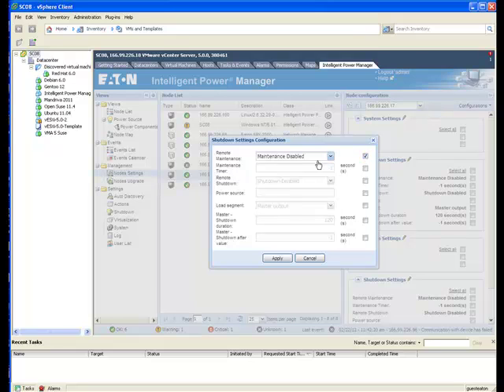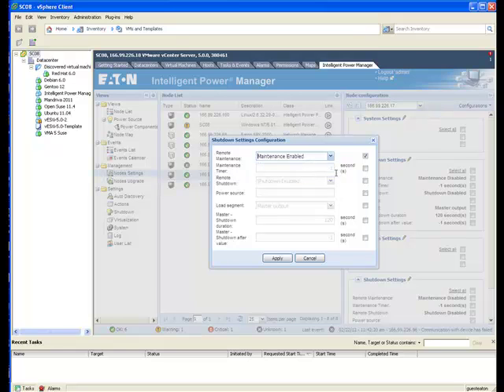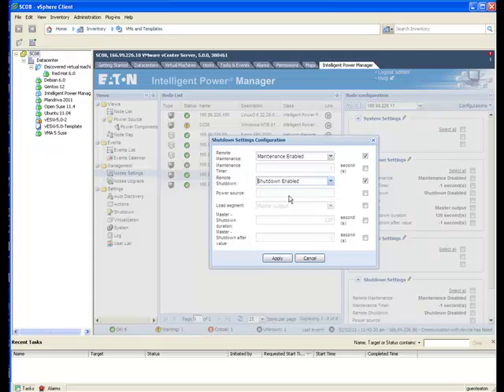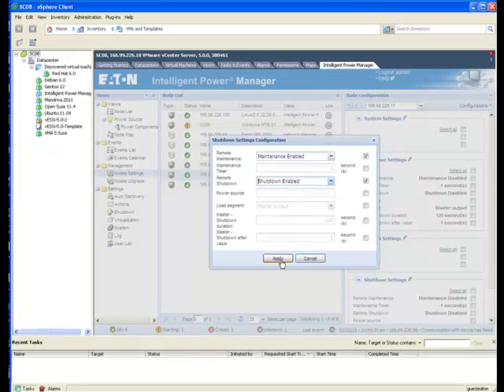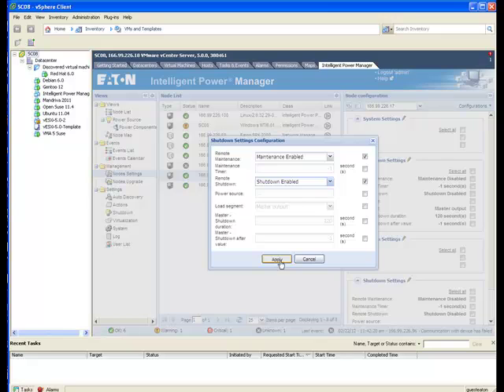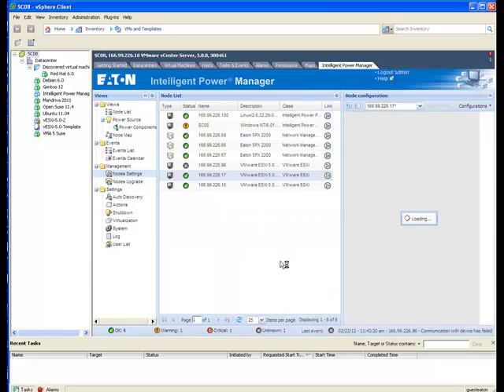For each server, you can enable or disable placement of the server into maintenance mode. Once the maintenance mode is selected, you can set the time for each server for when it goes into maintenance mode, then when the server actually powers down. With this important feature, you can stagger your server shutdowns to extend your battery on time.